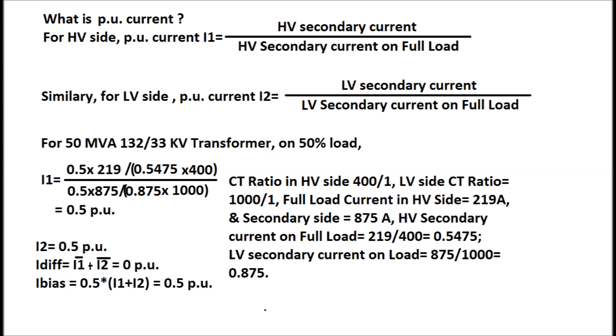For a 50MVA, 132/33kV power transformer at 50% load, I1 = 0.5 per unit and I2 = 0.5 per unit. The I-difference, being the vector sum of I1 and I2, comes to 0. The I-bias, being the average value of the sum of I1 and I2, comes to 0.5 per unit.